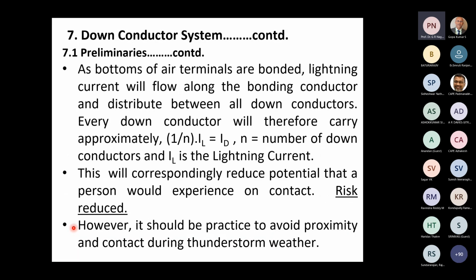Now, as the bottoms of air terminals are bonded, lightning current will flow along the bonded conductor and distribute between all down conductors. I am repeating this. Every down conductor will therefore carry approximately 1 by n of the stroke current, the lightning current IL, that is equal to ID. ID is the current in each down conductor. So this will correspondingly reduce the potential that a person would experience on contact. Risk is reduced. It may not be zero. It may not be just a few percent, but it can be significant. One has to estimate that.